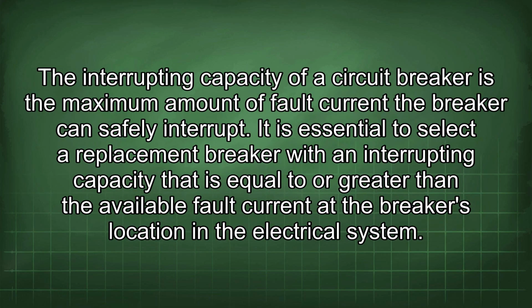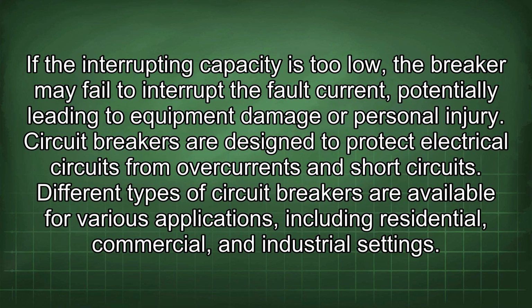The interrupting capacity of a circuit breaker is the maximum amount of fault current the breaker can safely interrupt. It is essential to select a replacement breaker with an interrupting capacity that is equal to or greater than the available fault current at the breaker's location in the electrical system. If the interrupting capacity is too low, the breaker may fail to interrupt the fault current, potentially leading to equipment damage or personal injury. Circuit breakers are designed to protect electrical circuits from overcurrents and short circuits.